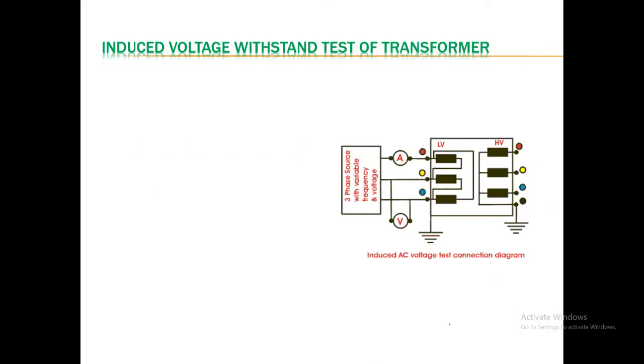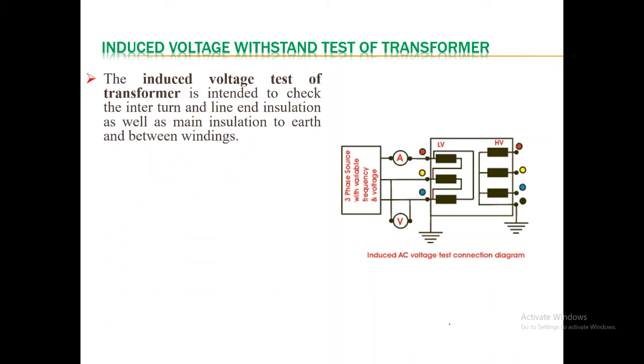Now let us see the induced voltage withstand test. This induced voltage withstand test is also known as the double frequency double voltage test. The induced voltage test of a transformer is intended to check the interturn and line end insulation as well as the main insulation to earth and between the windings. So this is the requirement of the testing.